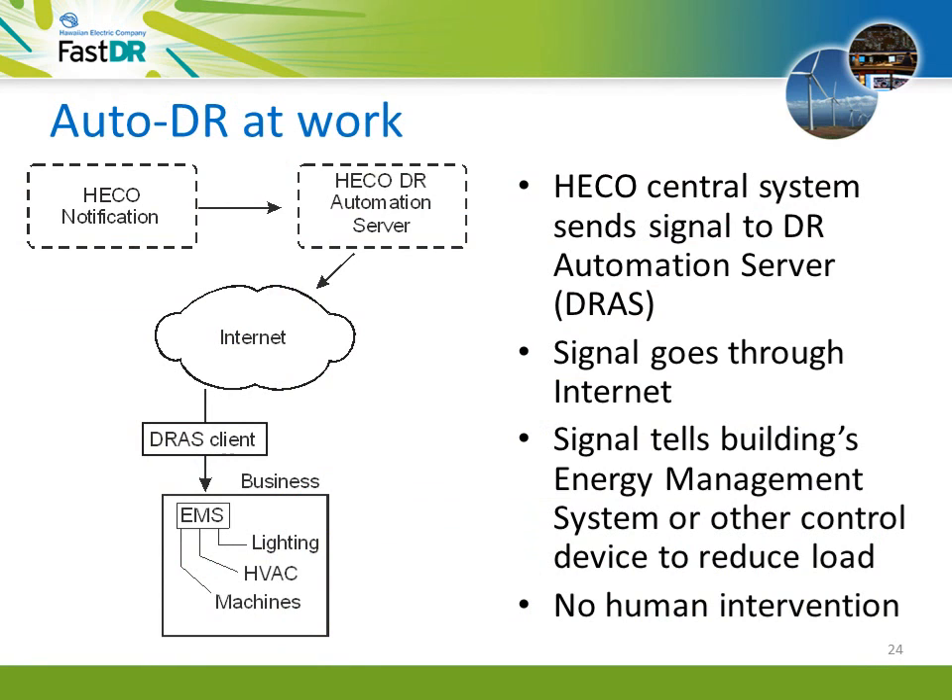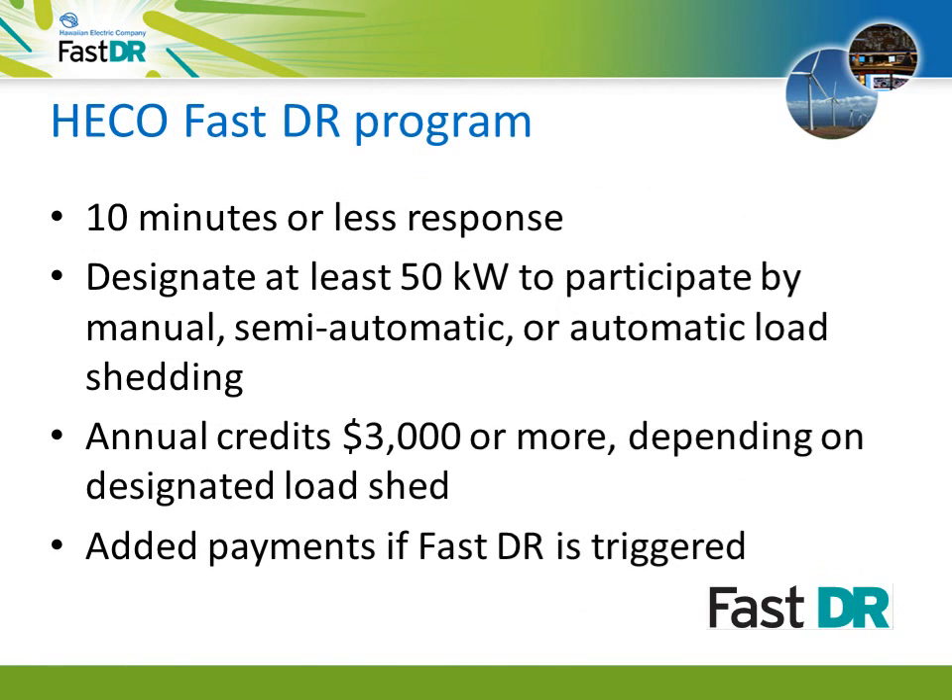Here's how auto DR works. Hawaiian Electric's central system operator initiates a DR event by triggering a control signal in a system called Demand Response Automation Server, or DRAS. The signal goes over the internet to a gateway at each specific facility. The DRAS client then conveys the message to the building's energy management system, which initiates load reduction strategies. FastDR means the load shed occurs within 10 minutes. To participate in FastDR, a business or facility must be able to designate at least 50 kilowatts of load that can be shut off or shed manually, semi-automatically, or by auto DR. Annual credit starts at $3,000 and can be as much as tens of thousands of dollars for more load shed.